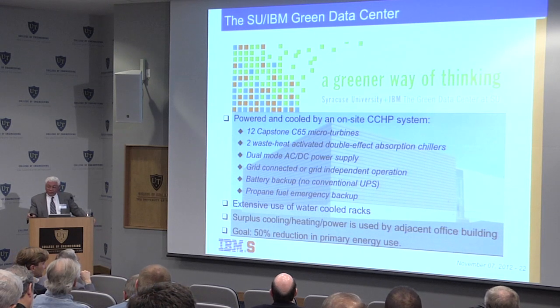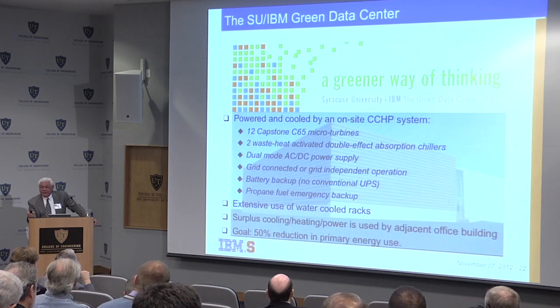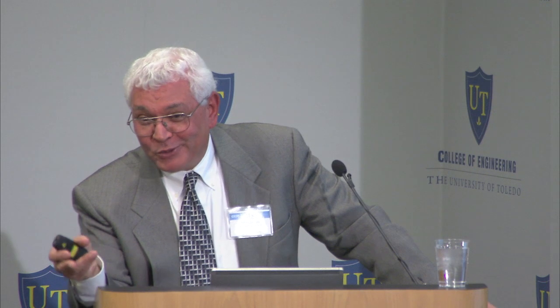Extensive use of water-cooled racks. Almost every rack we have in our data center is water-cooled on the rack level. Roger showed you pictures where you're doing water cooling on the module level, inside the boxes, inside the computers themselves. This is water cooling on the rack level. There are a couple of advantages to this. The closer you bring the cooling to the source of heat, the more efficient your system will be. Obviously, if you bring the cooling directly to the chip, that will be the most efficient way of cooling it.